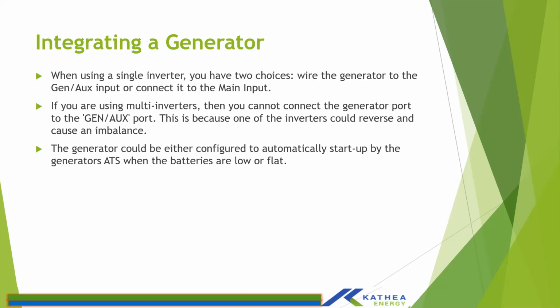The system, as you have said, can actually output an ATS signal, which can be used to start up the generator when the batteries are running low, or in a scenario where you are off grid. You can set, let's say you want to always keep your battery high, and then run your generator. The moment the system loses grid, then it can activate the ATS for a specified runtime. So we'll look into that in detail in our commissioning session tomorrow as well.